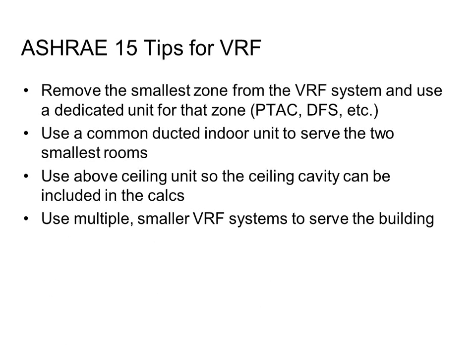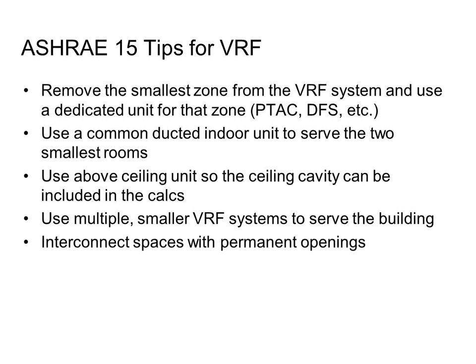I can use smaller systems. Instead of one 30-ton VRF for this building, maybe I have to use two 15-ton systems. Or maybe I want to use three 10-ton systems to do the job, right? That way each circuit, if you will, is smaller, and I will have less likelihood of hitting that RCL limit.